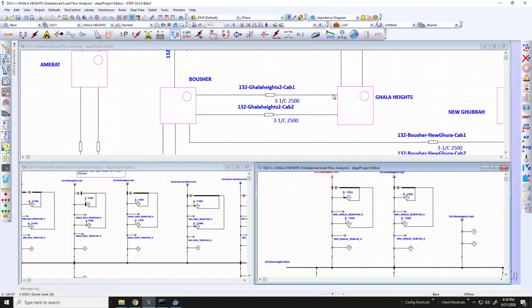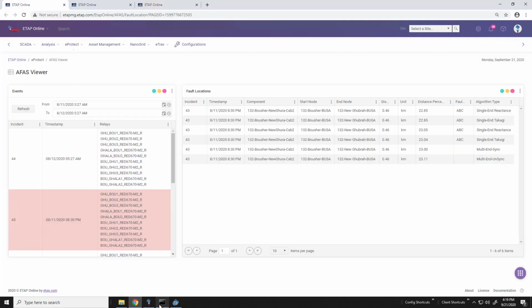Additionally, on the other side, if I zoom into this network, here I can see another set of relays that are defined on that transmission line, and then again, another transmission line with its own set of relays. So we have a number of different relays feeding a number of different lines in that substation. The beauty here is we can take as many relay COMTRADE files from the system and correctly assign the fault location. So in this example, I'm going to pull up our AFAS viewer.